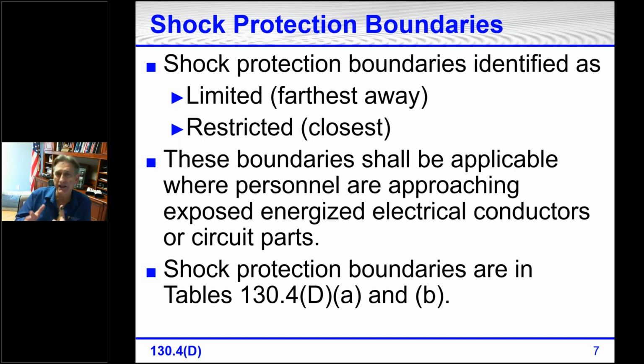There are certain things that you do or do not do before crossing the limited approach boundary. There are certain things that are done or not done before crossing the restricted approach boundary. These are called triggers. For example, before crossing the restricted approach boundary, if you're taking tools with you, the tools have to be voltage rated. So there was no trigger in place for the prohibited approach boundary, so that boundary was eliminated. So the two boundaries shall be applicable where personnel are approaching exposed energized electrical conductors or circuit parts.